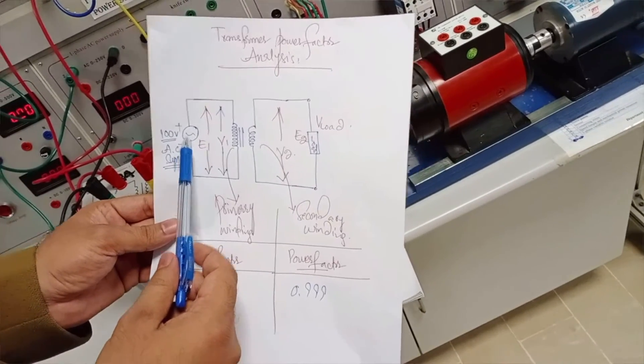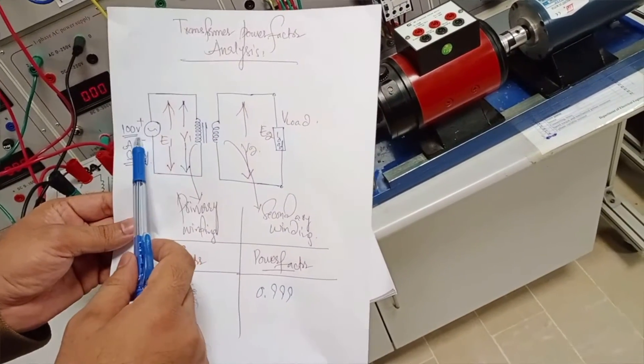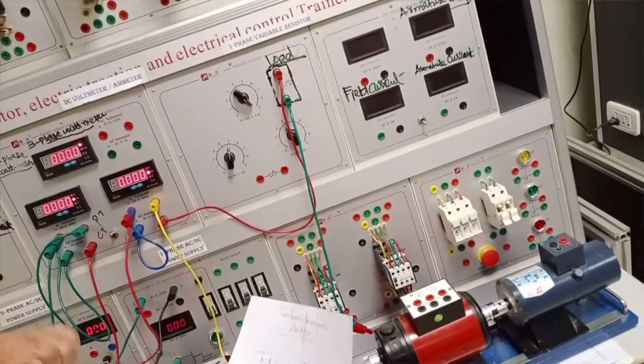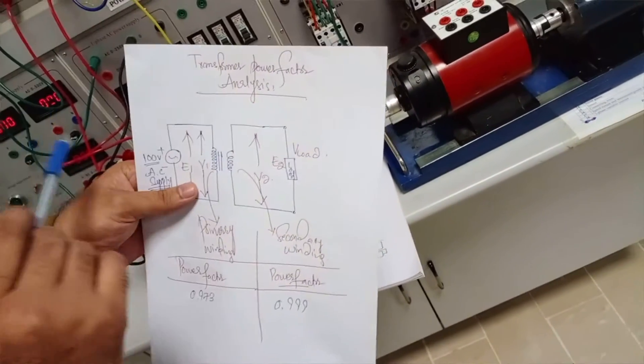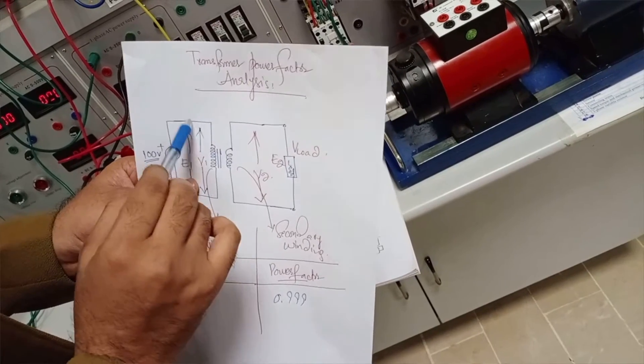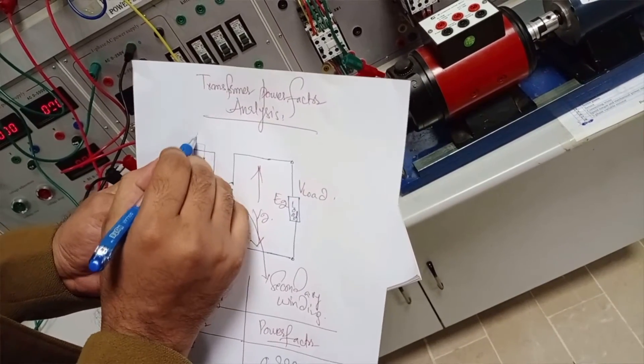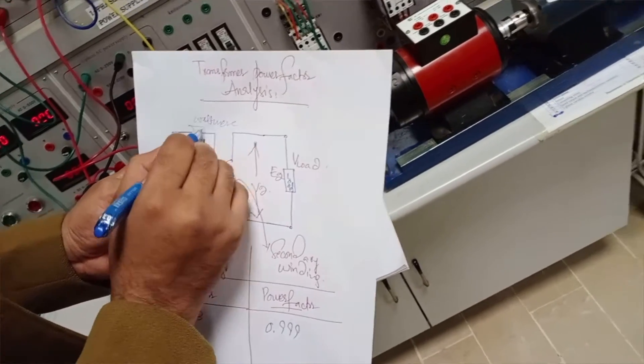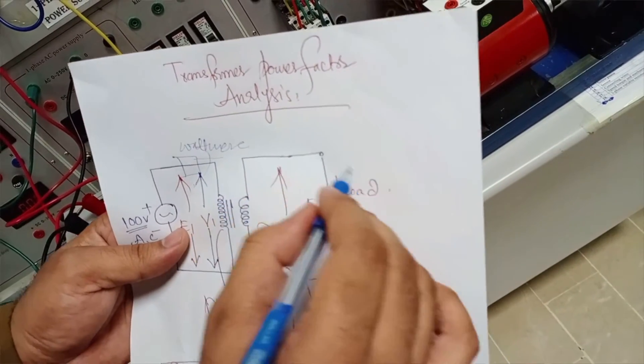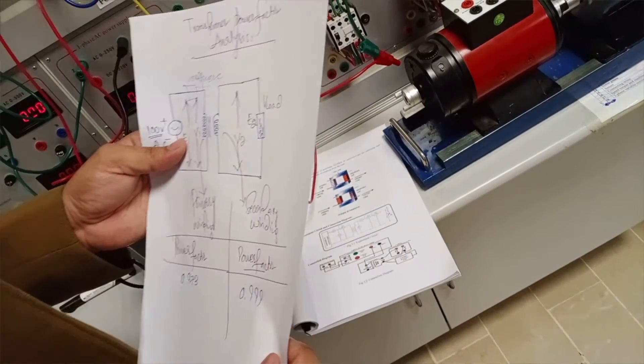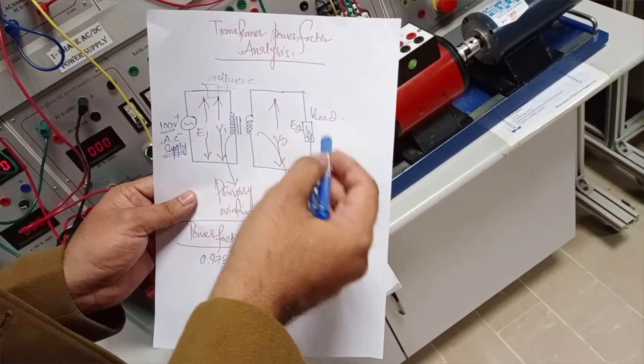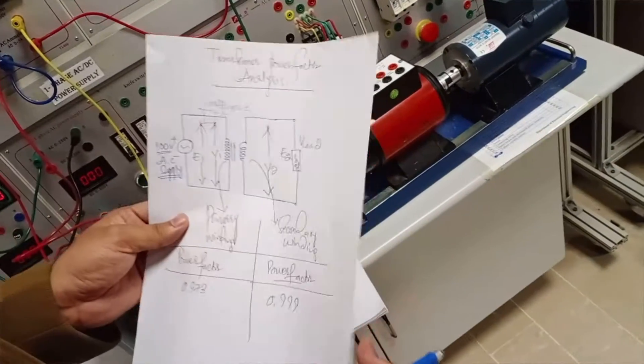The primary of the transformer is connected with the primary voltage source, and the secondary of the transformer is connected with the load side. In between these two windings we need to connect the watt meters. The first watt meter will give us the primary side power factor, and the secondary watt meter connected with the secondary winding will give us the secondary side power factor, which will be close to unity because a resistive load is connected.